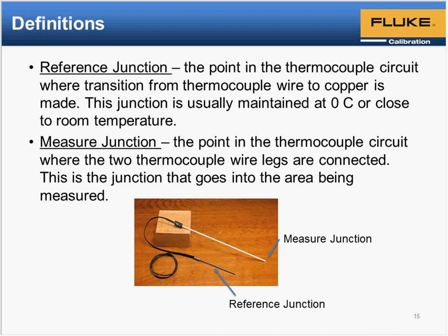So how often should you measure inhomogeneity? Well, it depends on the level of uncertainty that you are trying to achieve with your thermocouples. If you're trying to go beyond the ASTM specs, then you have more obligation to measure inhomogeneity. Definitely, if you're seeing errors with your thermocouple wire, that'd be one of the first things you want to do, just do a quick inhomogeneity test, if you just need to get rid of the wire.